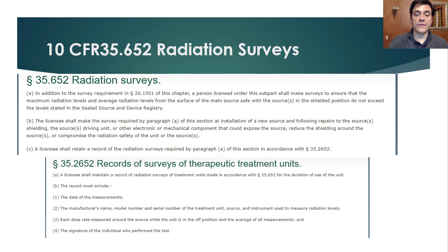This survey required by paragraph A above that we just discussed should happen following the repair to the source shielding, or the source driving unit, or other electrical or mechanical components. So the records need to be kept as 35.2652, and that is for the duration of the use of the unit. So for different records, there is different durations.